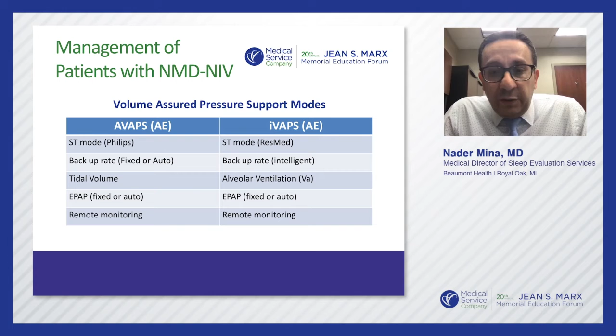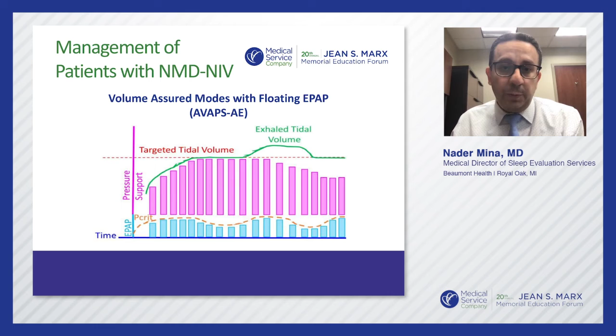This diagram basically explains the AVAPS, how it works, and as you noticed in the EPAP graph, you see that the EPAP will adjust to maintain the patency of the airway. As you see here, it goes up and down. And the pressure support, once you hit the target tidal volume, it continues to go down. If you drop below the targeted tidal volume, the pressure support will go up. So it's an auto EPAP plus an auto pressure support to allow the patient to maintain a predictable tidal volume. At the same time, they treat their obstructive events by an auto EPAP feature.